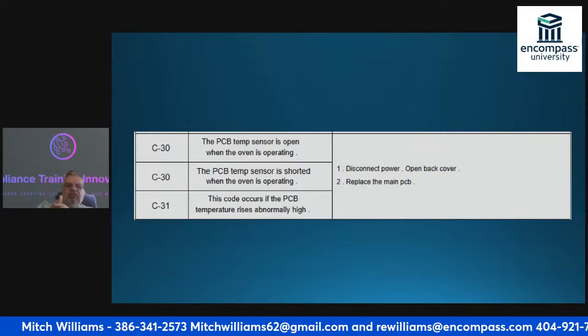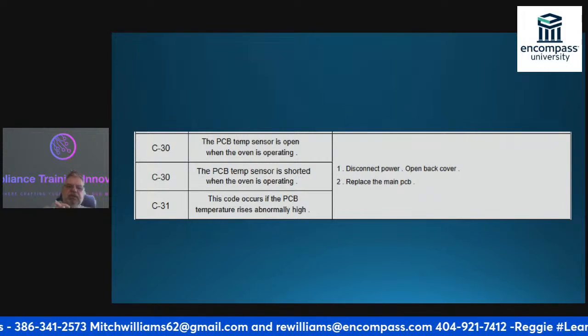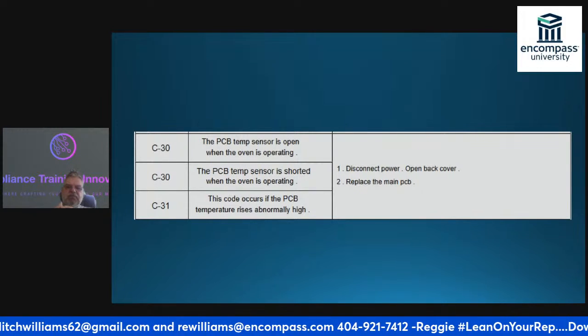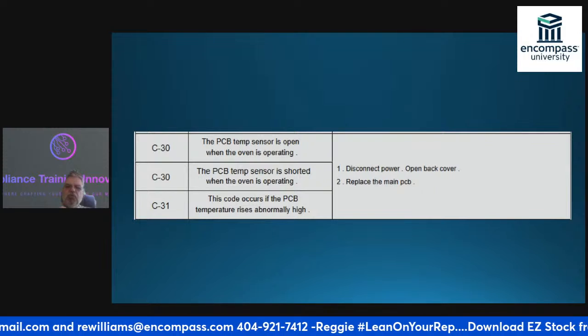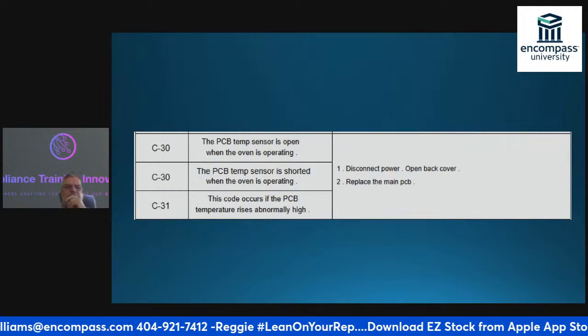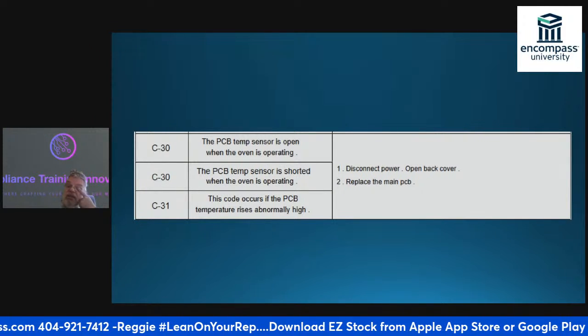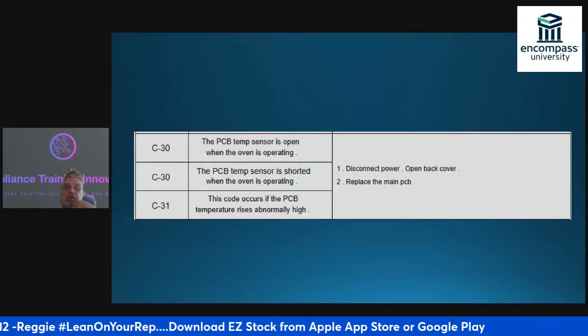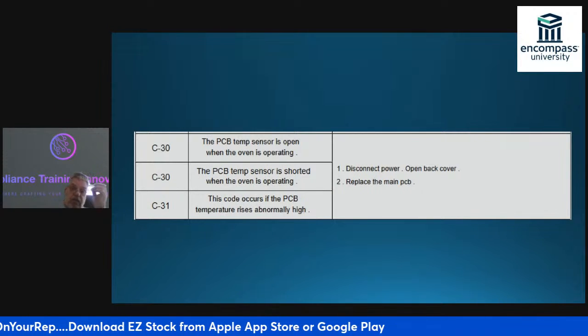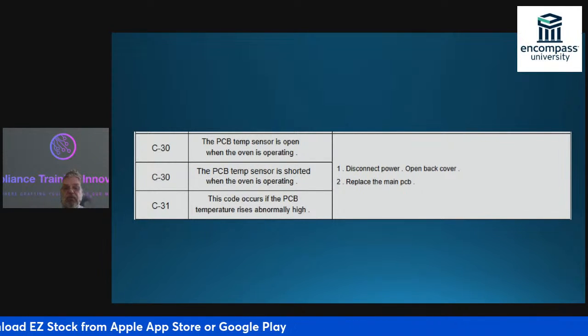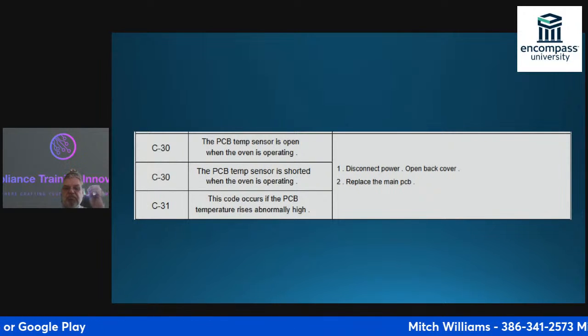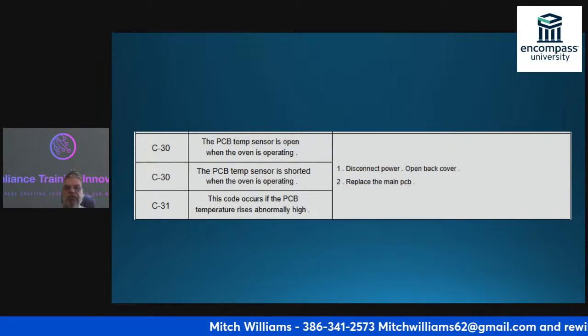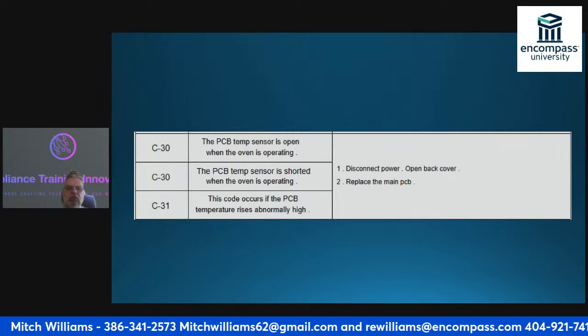Okay, so if I have a C30, it tells me that the PCB temperature sensor is open, and I'm going to have to replace the sensor. If I get the other one, it could also be that it is shorted whenever I'm trying to operate it. If I get a C30, it could tell me that the PCB temp sensor is shorted whenever it's being operated. So it could be open or shorted.